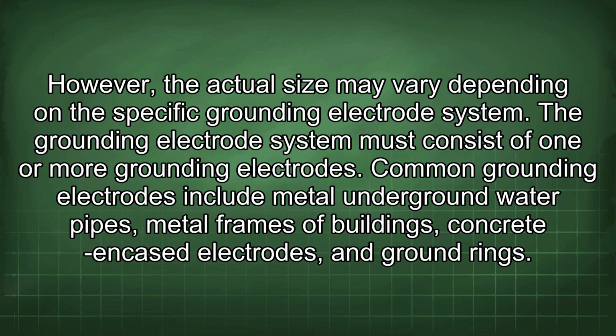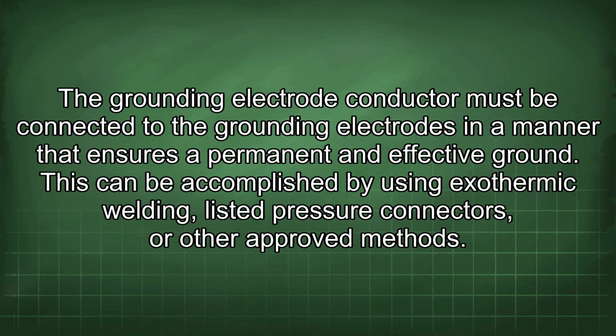The grounding electrode system must consist of one or more grounding electrodes. Common grounding electrodes include metal underground water pipes, metal frames of buildings, concrete encased electrodes, and ground rings. The grounding electrode conductor must be connected to the grounding electrodes in a manner that ensures a permanent and effective ground. This can be accomplished by using exothermic welding, listed pressure connectors, or other approved methods.